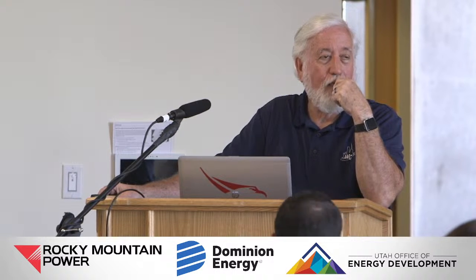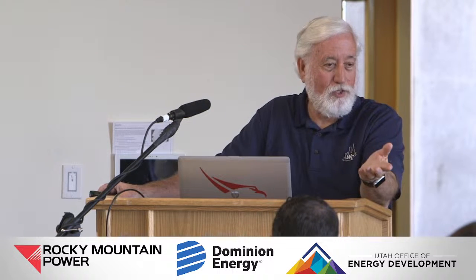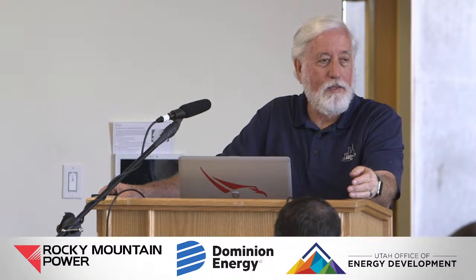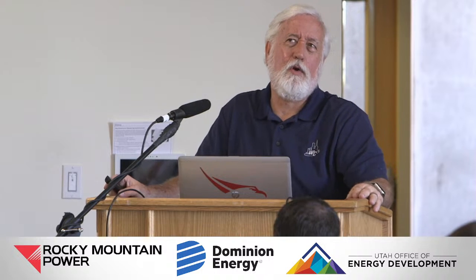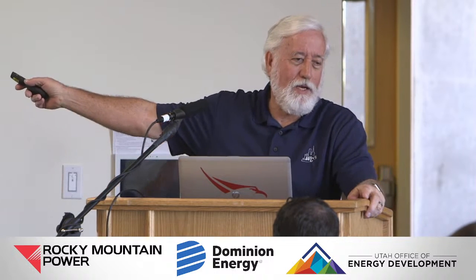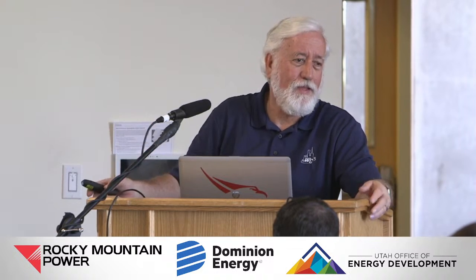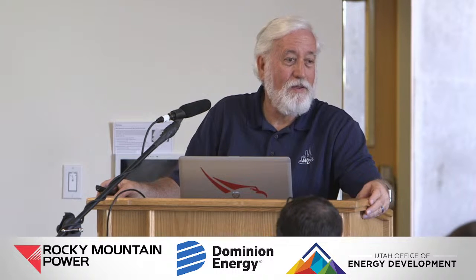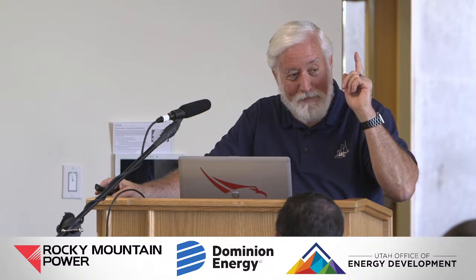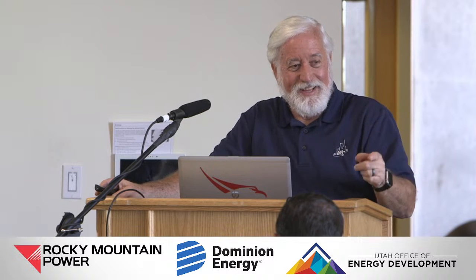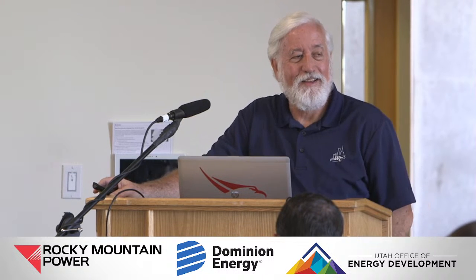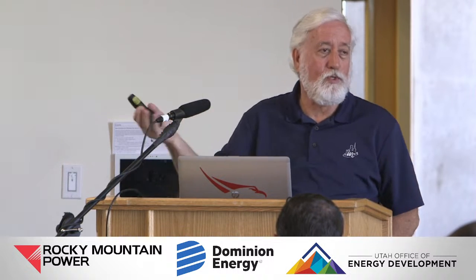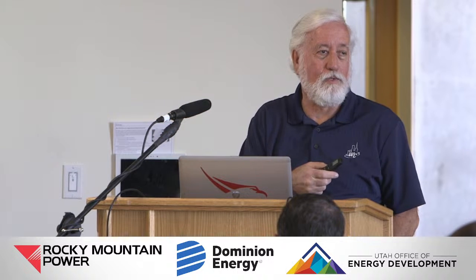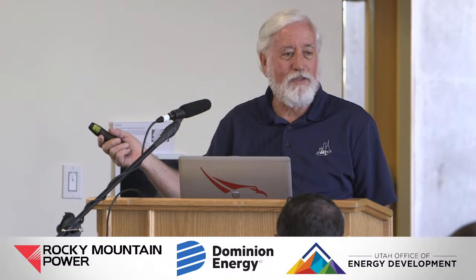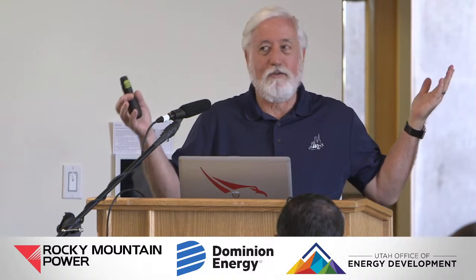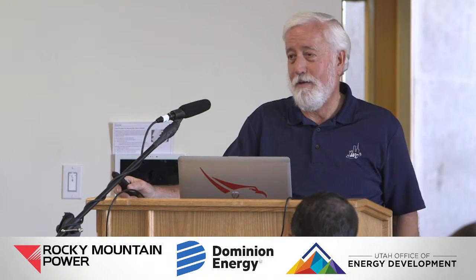Have that there? Yeah. I mean, it's only logical, isn't it? It makes so much more sense. And they say, well, electric water heating's expensive. How much water are we heating, for heaven's sakes? How much are you using that recirc pump? How much power is going into just the pump motor? It runs 24/7. Even if it's on a time clock, it's just a huge amount of energy that's being wasted in those. You slap a little one underneath, sized for how many fixtures you have under there.